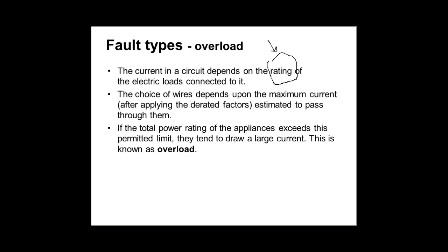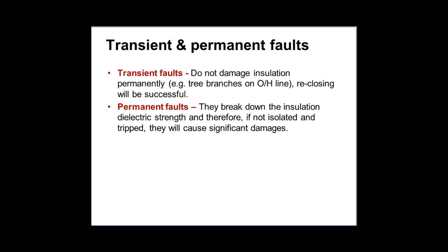So what is expected from the system is that you would expect this protection system to operate pretty quickly, either fuse protection or relay protection. This overload is what we call, let's get back to the beginning, incipient fault. So what's that? A fault that takes a long time to develop into an insulation breakdown, normally caused by partial discharge or long-term overload.